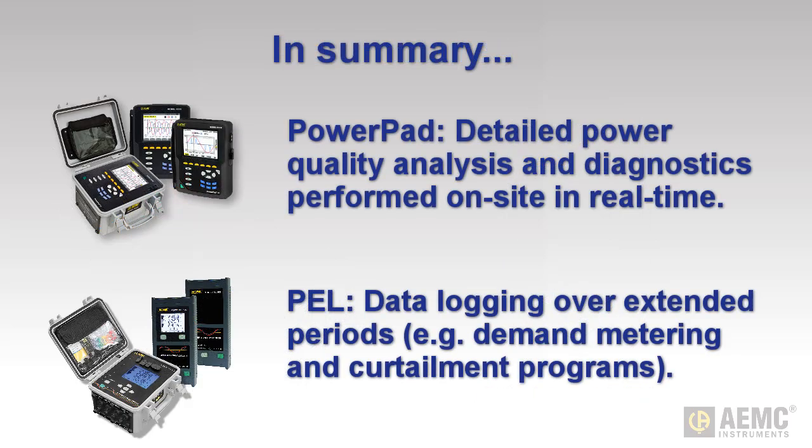In summary, PowerPad instruments are optimal for applications involving detailed power quality analysis, especially those that require capturing short-duration anomalies. If your primary focus is performing on-site analysis and diagnostics in real-time, the PowerPad is the best choice. The PEL, on the other hand, is ideal for recording energy and power quantity measurements and large amounts of data while operating unattended for long durations in environments with limited space and access.